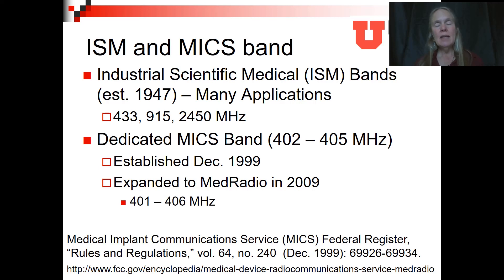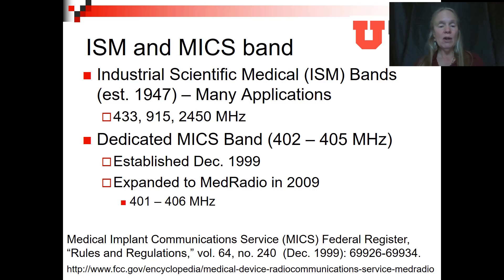We also needed a standard for frequency. The Industrial Scientific Medical, or ISM, bands had been established in 1947 for many applications. In bioelectromagnetics, the particular bands found important were 433, 915, and 2450 megahertz. In 1999, a dedicated MICS band from 402 to 405 megahertz was established — the Medical Implant Communication Services band, dedicated for this particular application.